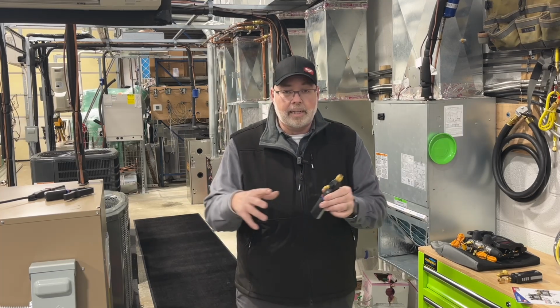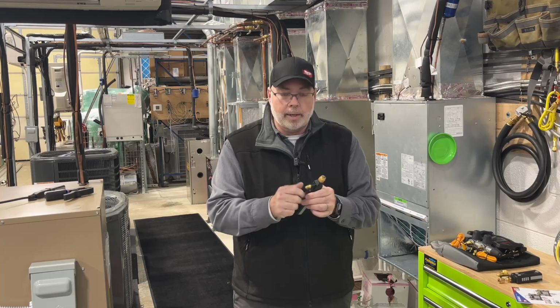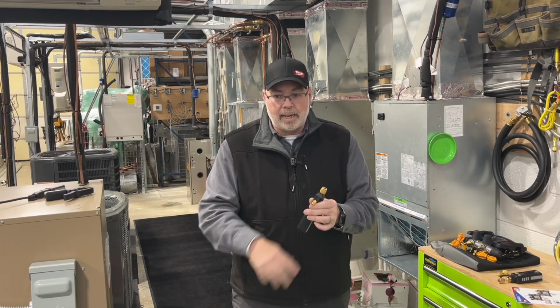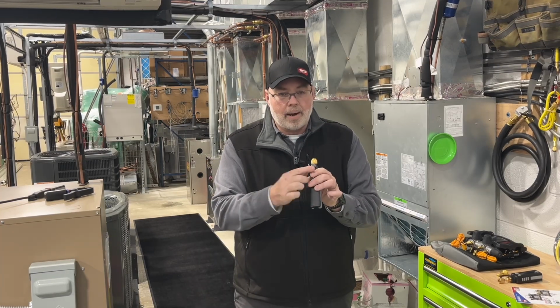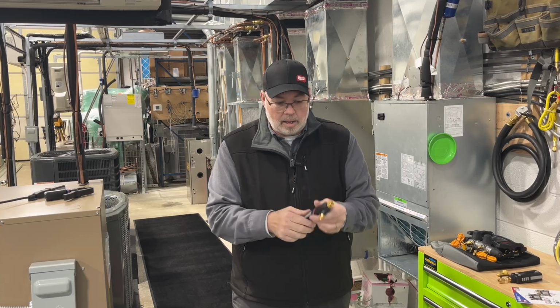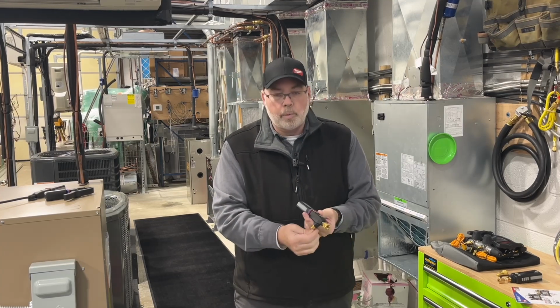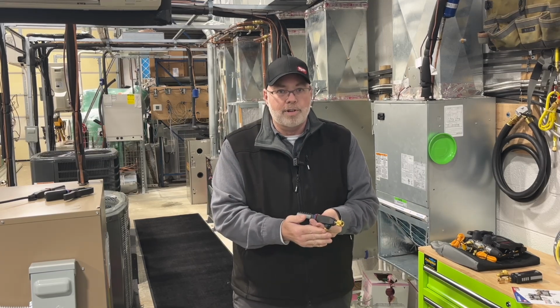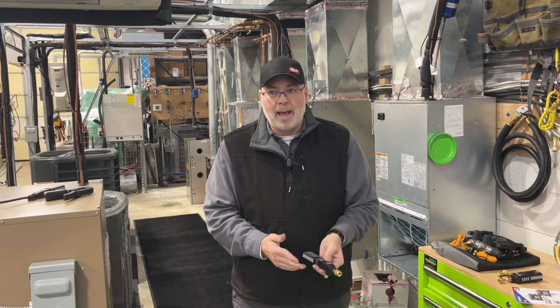I'd recommend getting a hose that's got a ball valve on it. You'll be able to connect to your refrigerant tank, and connect here on the one you have on the suction side, and you'd be able to actually add refrigerant right through the probe without having to go back and get a manifold set.